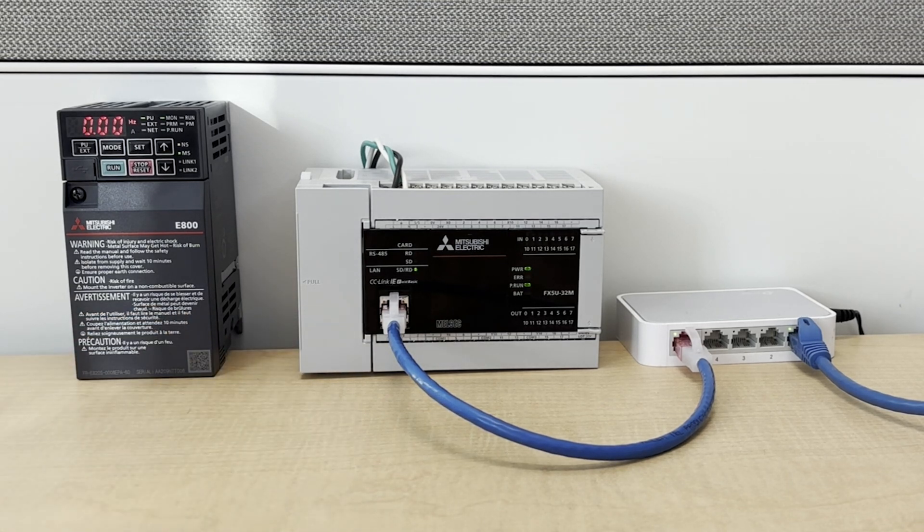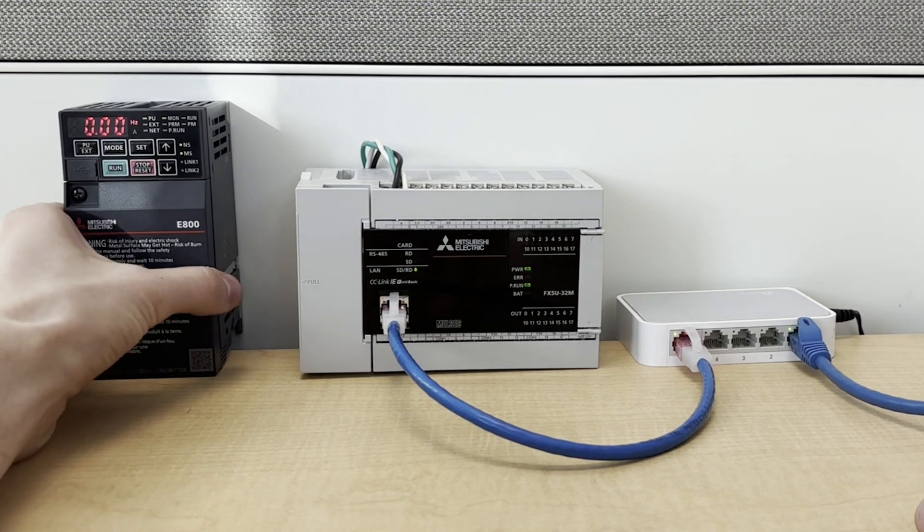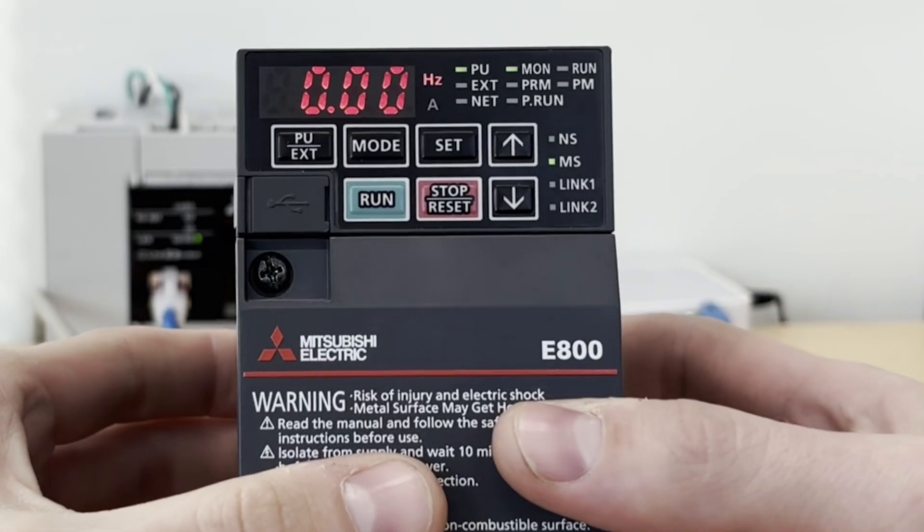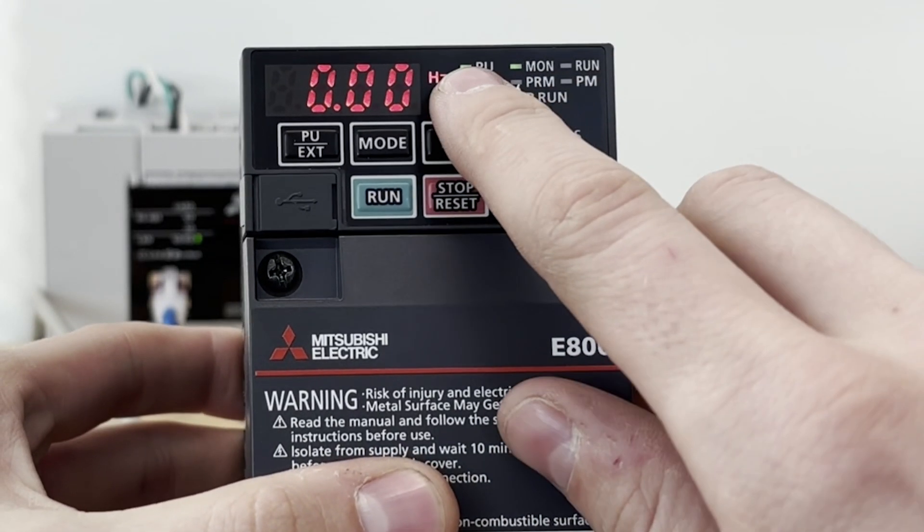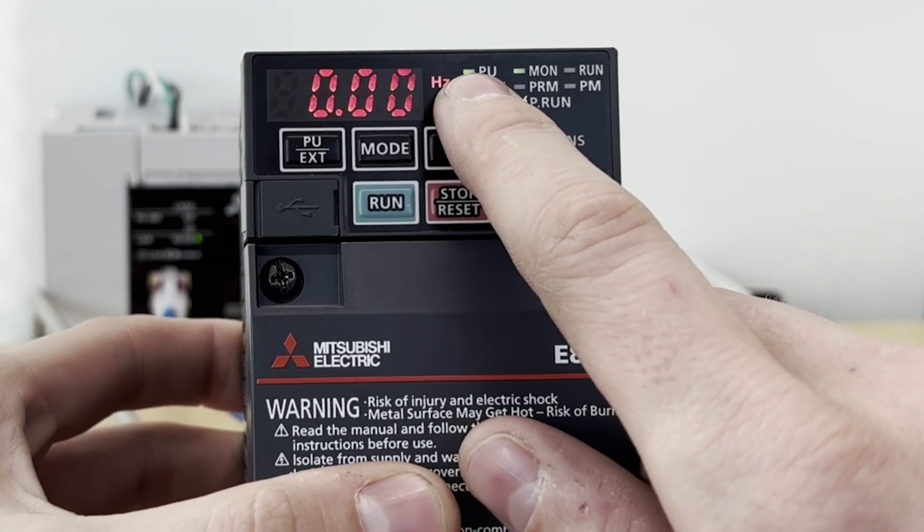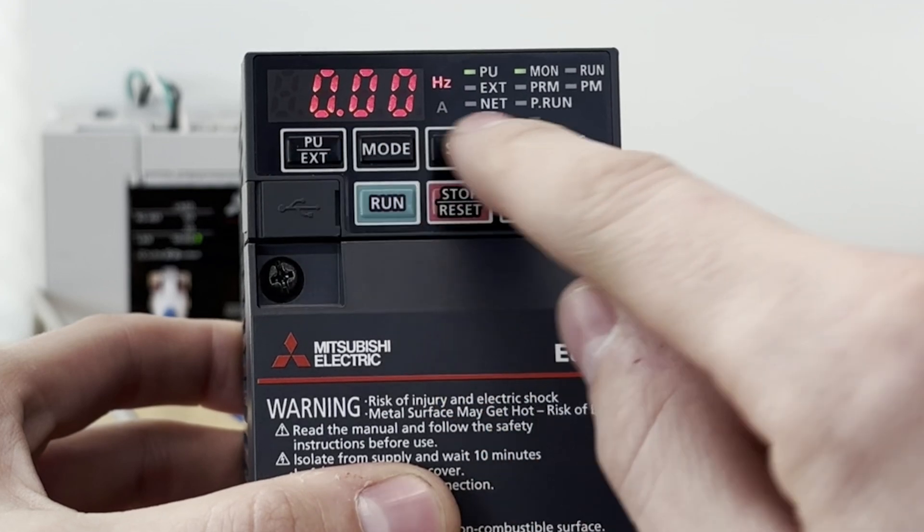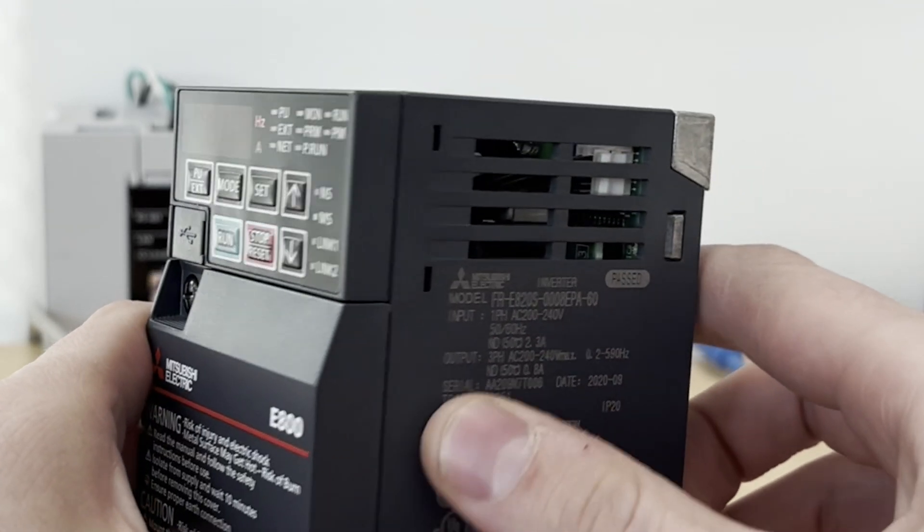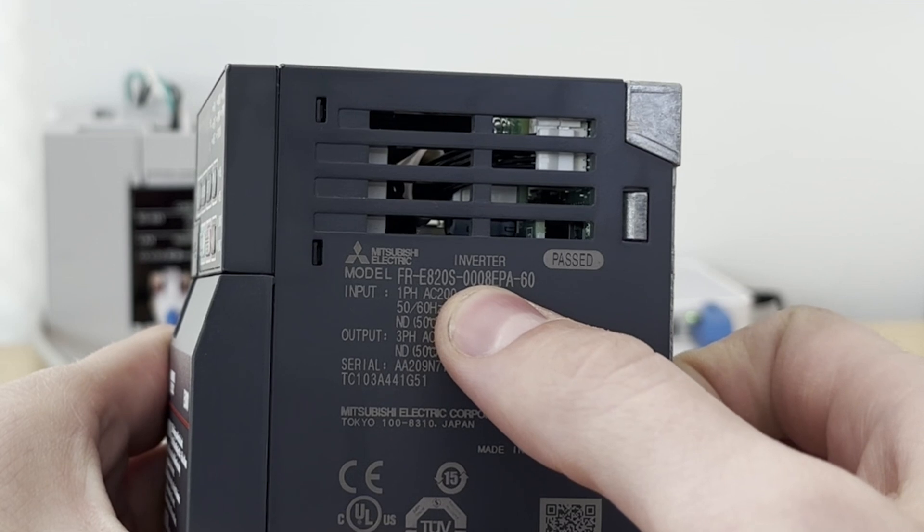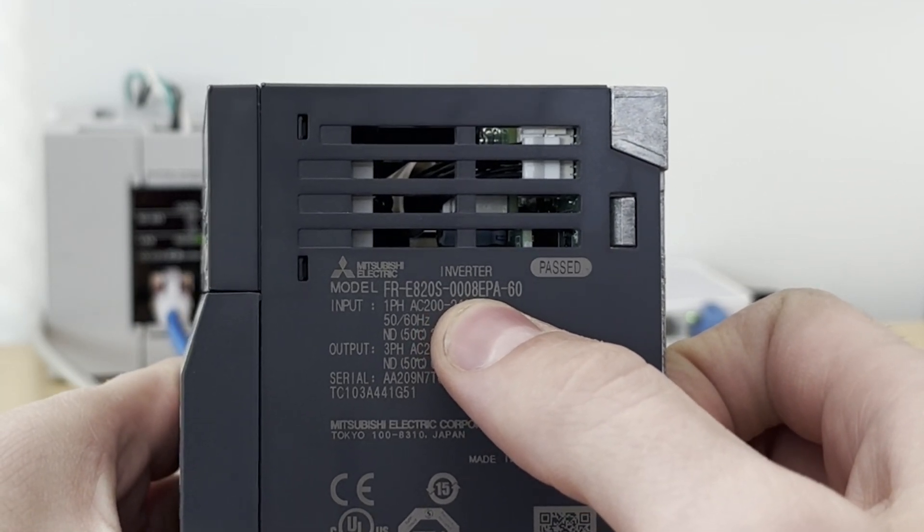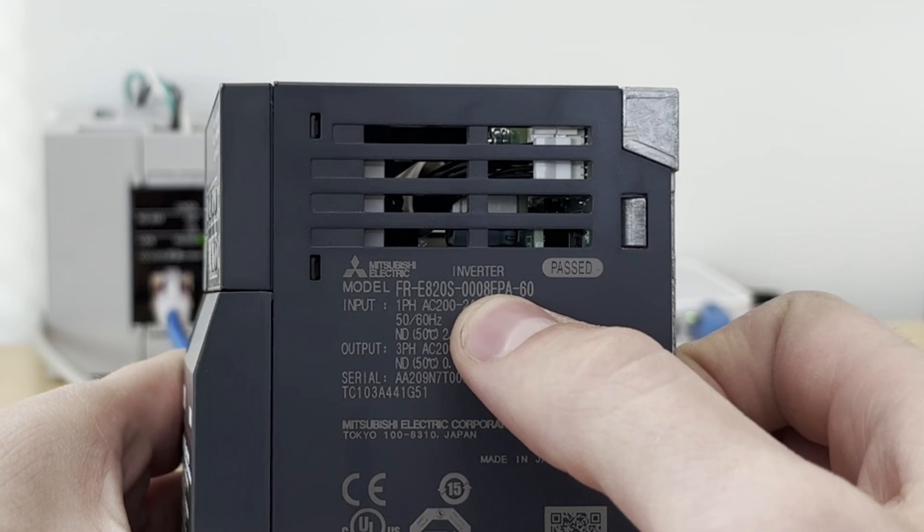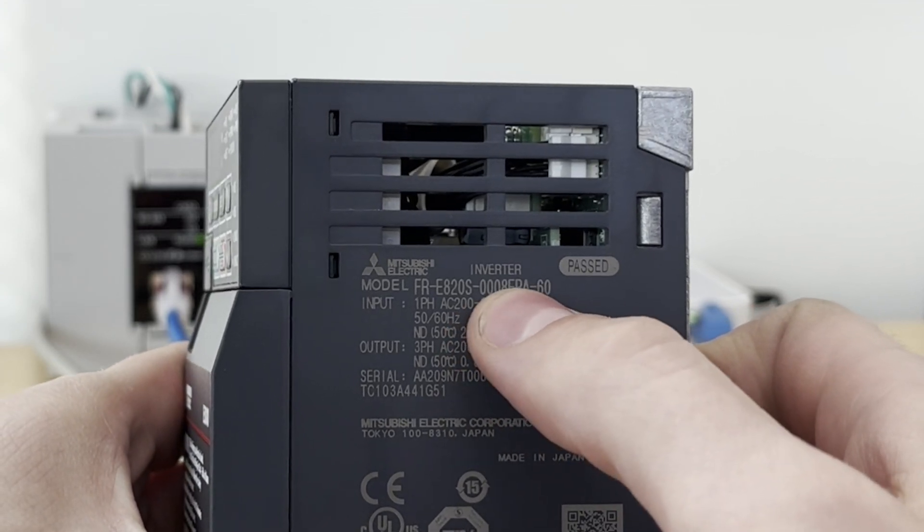So the first thing that we're going to want to do is set up the parameters on our inverter. You want to make sure your inverter is in PU mode. That stands for parameter unit. That will allow us to set the parameters using the buttons on the face of the unit. Note that this is an E800E series inverter. This E in the part number stands for Ethernet, allowing this module to be controlled via Ethernet.